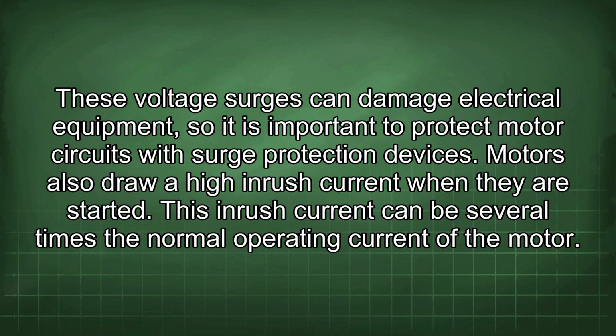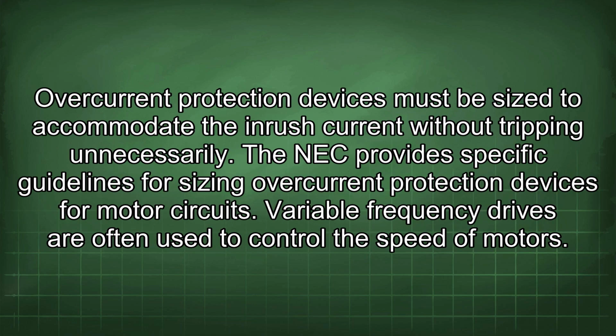Motors also draw a high inrush current when they are started. This inrush current can be several times the normal operating current of the motor. Overcurrent protection devices must be sized to accommodate the inrush current without tripping unnecessarily. The NEC provides specific guidelines for sizing overcurrent protection devices for motor circuits.